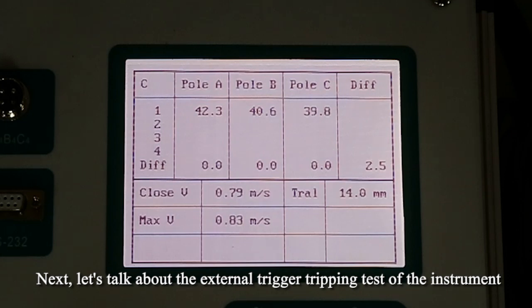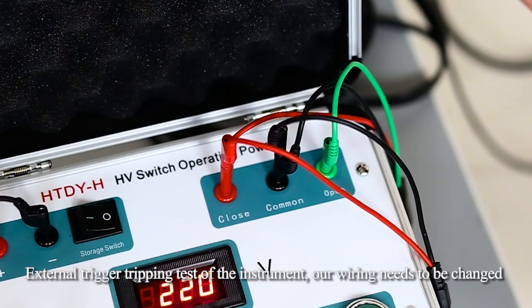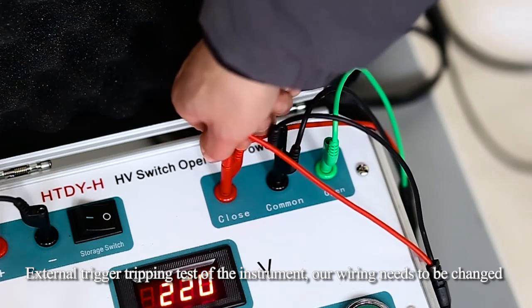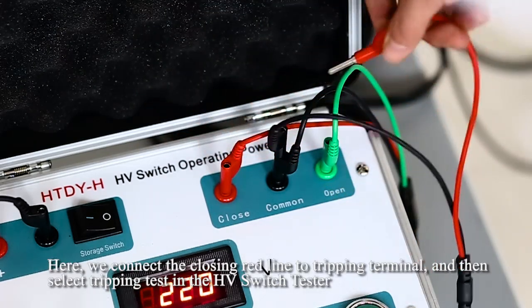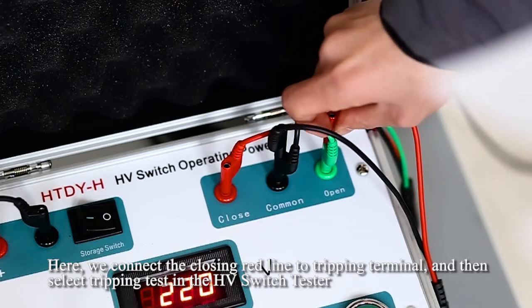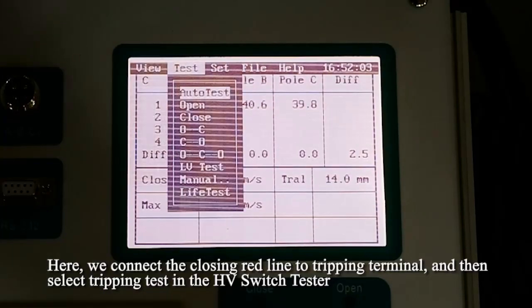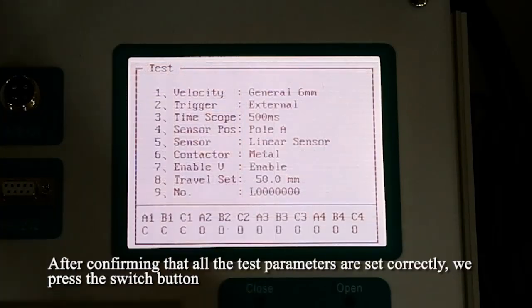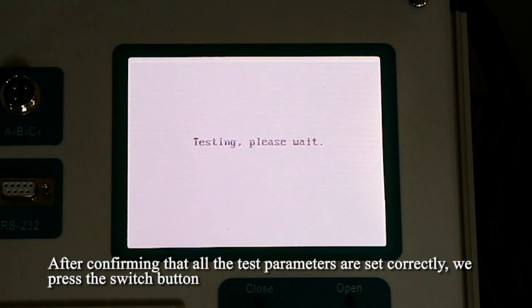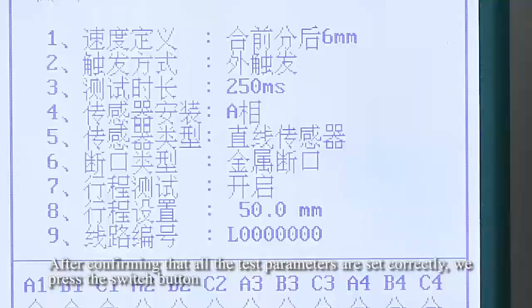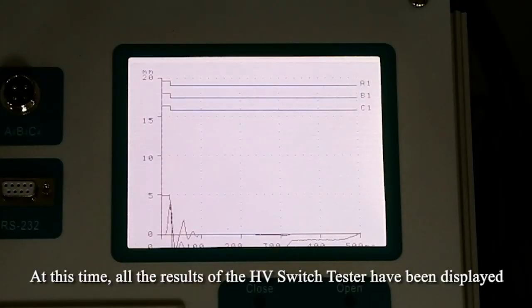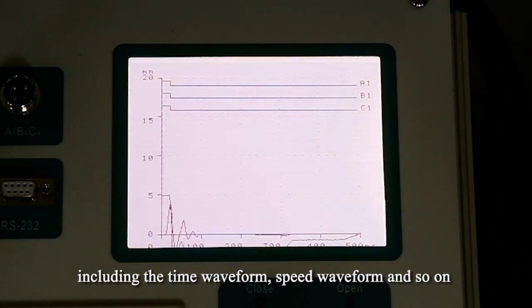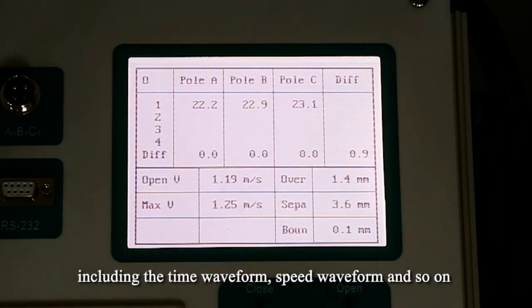Next, let's talk about the external trigger tripping test of the instrument. Here, we connect the closing red line to the tripping terminal and then select the tripping test in the high voltage switch tester. After confirming that all the test parameters are set correctly, we press the switch button. At this time, all the results are displayed on the high voltage switch tester, including the time waveform, speed waveform, and so on.